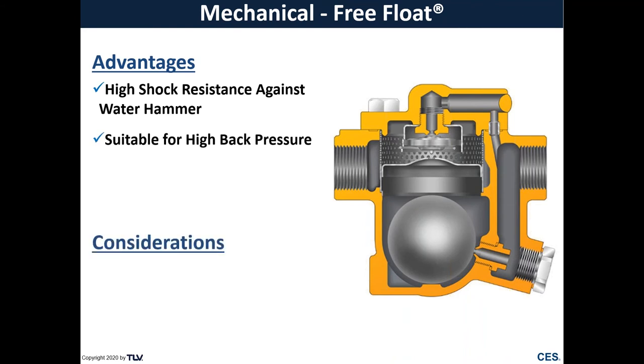Some considerations to think about when installing this trap, because there's the float, it needs to seat against the orifice properly. It is sensitive to installation orientation.